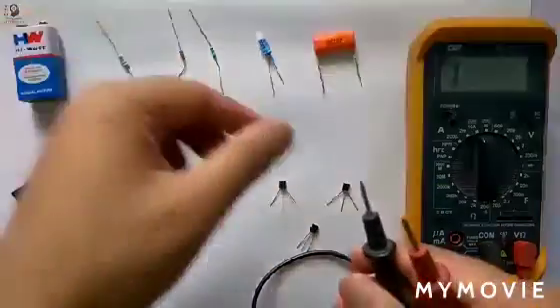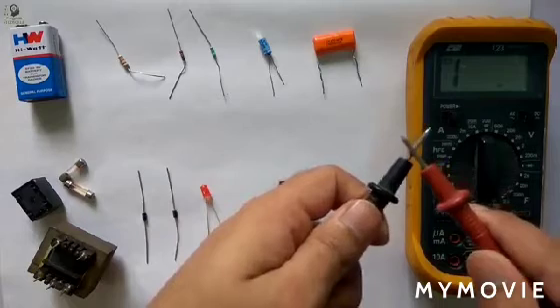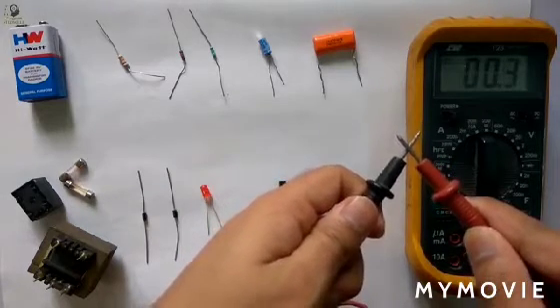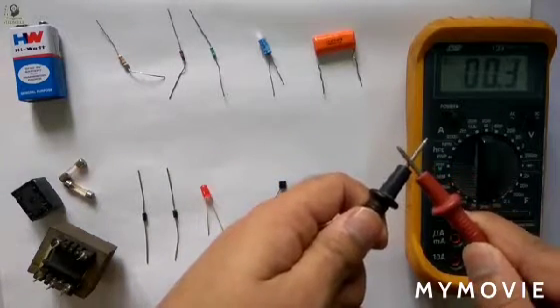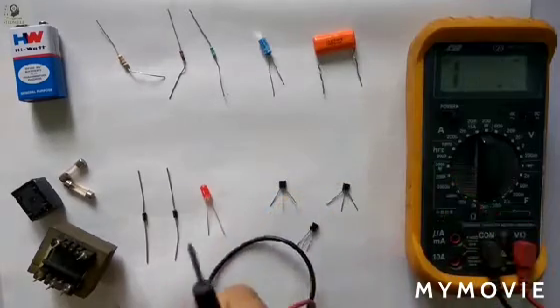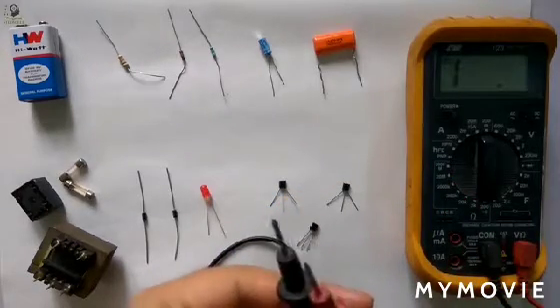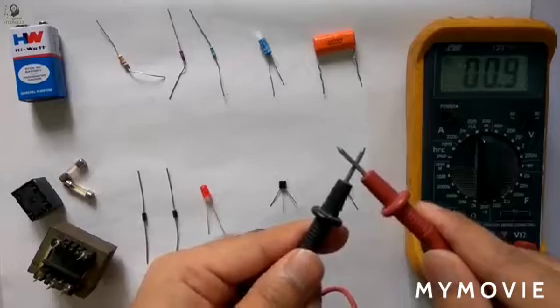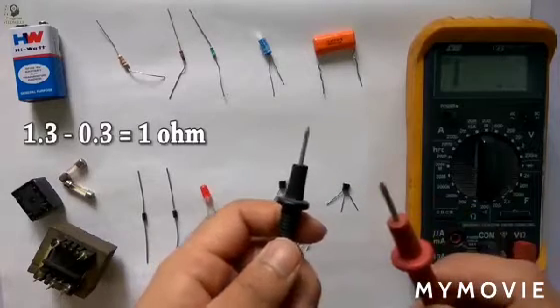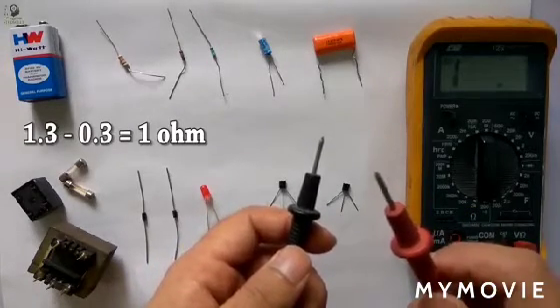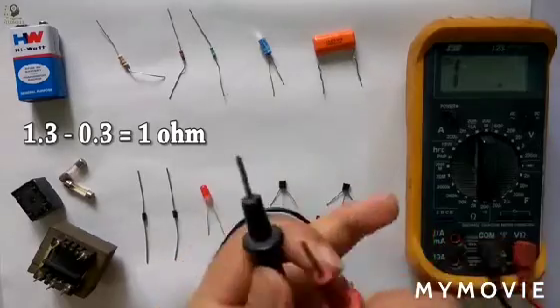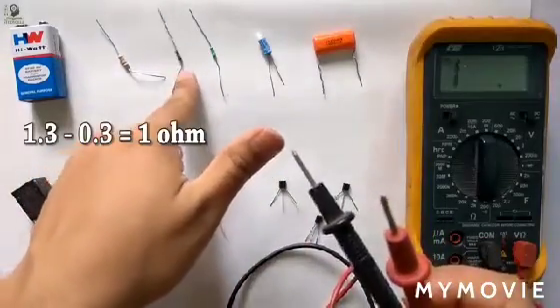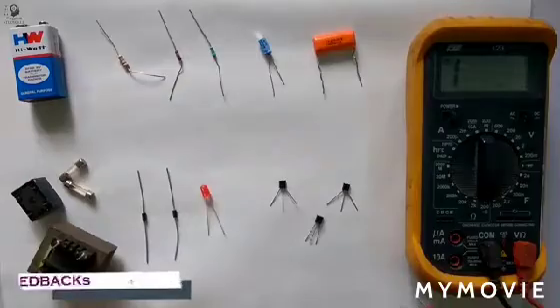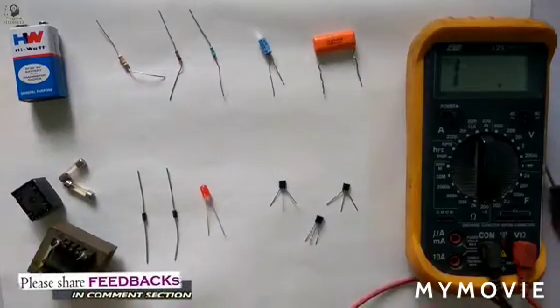Now what I have to do is connect these two leads together to measure the lead resistance, and it's showing 0.3 ohm. Previously we got the result 1.3. Now the lead resistance is 0.3. If I subtract 0.3 from 1.3, we will get exactly 1 ohm, which is the nominal value of this resistance. Thus we can accurately measure the lower value resistance.